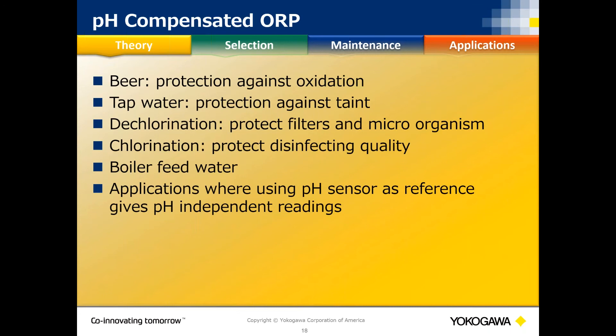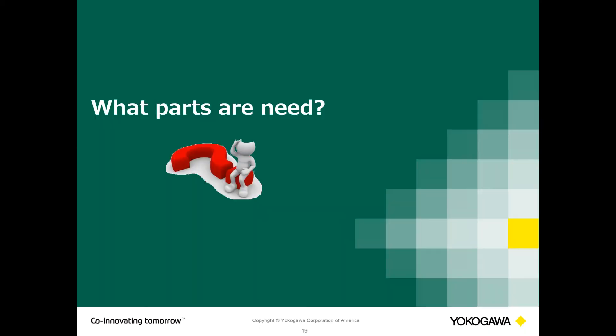pH compensated ORP is used in applications like beer brewing for protection against oxidation, tap water, dechlorination, chlorination, and boiler feed water — anywhere where pH is also changing and affecting ORP readings. Using the pH glass as a reference ensures the millivolt values seen are due to the oxidation reduction of the chemical being monitored, not artifacts of pH change.